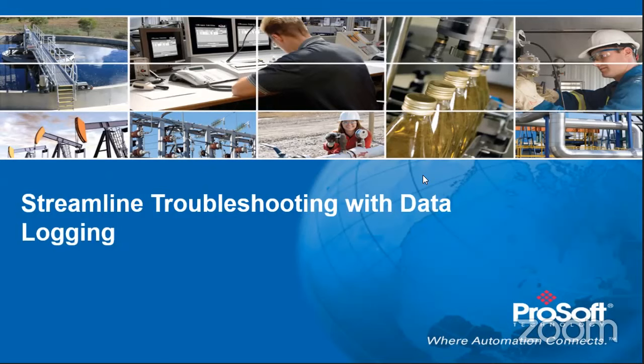So all that data then gets transferred to the ProSoft module. Yep. Basically the data lands first into Logix, and then Logix, through the add-on instruction, pushes that information to the coprocessor. The coprocessor runs the API calculations and then passes the results back to the processor.